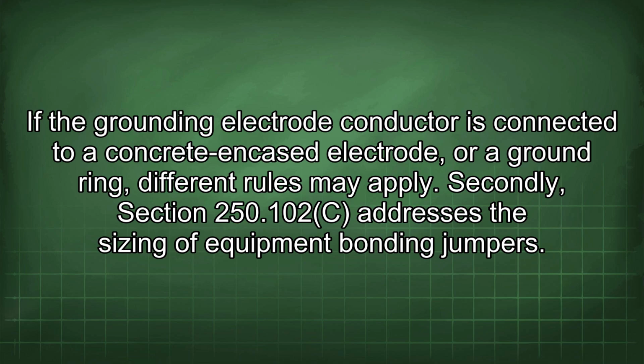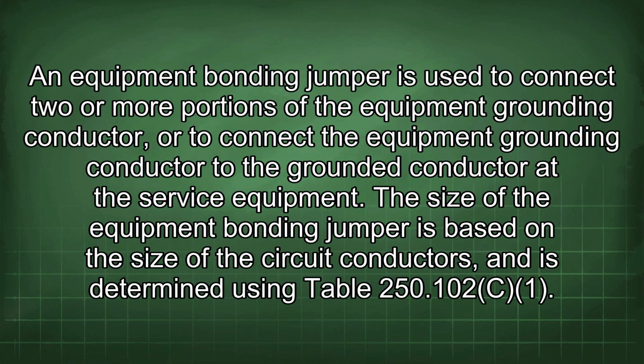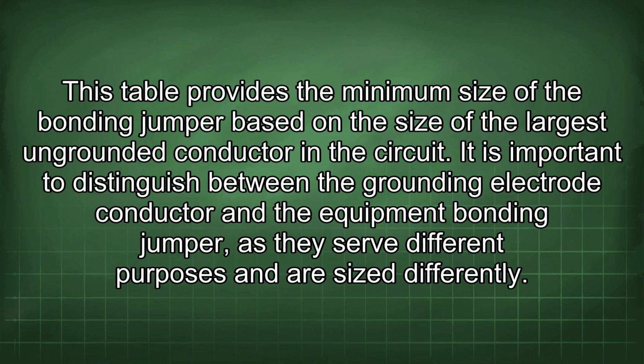250.102(C) addresses the sizing of equipment bonding jumpers. An equipment bonding jumper is used to connect two or more portions of the equipment grounding conductor, or to connect the equipment grounding conductor to the grounded conductor at the service equipment. The size of the equipment bonding jumper is based on the size of the circuit conductors and is determined using table 250.102.